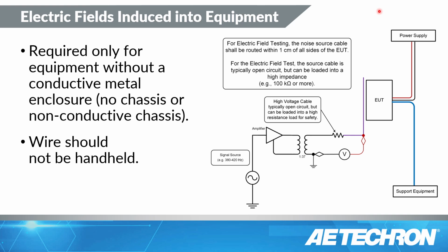Or you can touch the chassis of the equipment, and we'll definitely not want that either. So most people will take this exposed wire and place it inside something like a plastic tube, or tape it to the side of a dowel, and then tape off the ends, so you're creating a safety at the end of the wire. And then you again sweep all sides, front, left, right, back, and top in 2 axes, left and right, and up and down. And then you also want to make sure that you're measuring the voltage. So some type of voltmeter capable of handling 170 volts, most of them are, to assure that you've got the right level of testing.